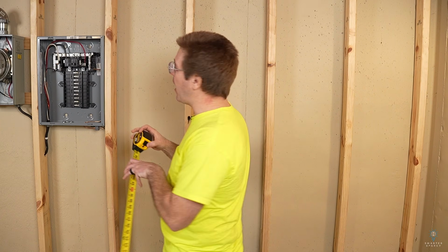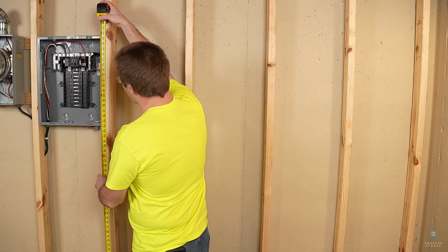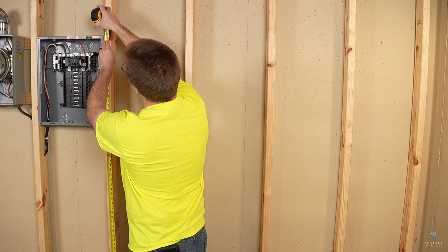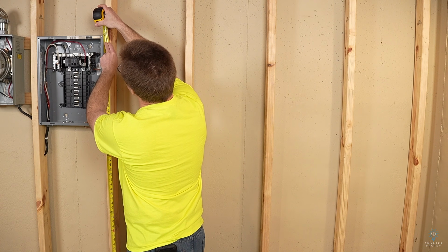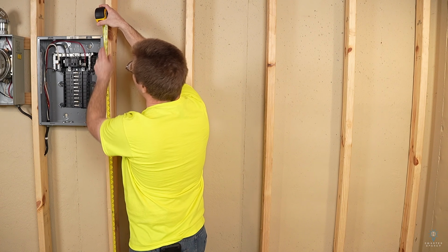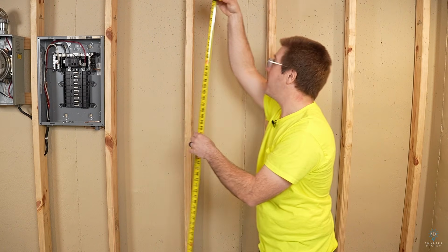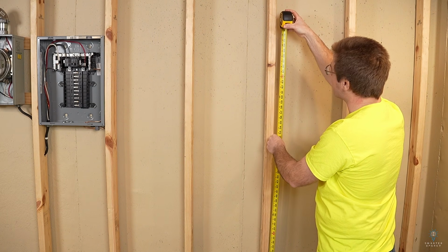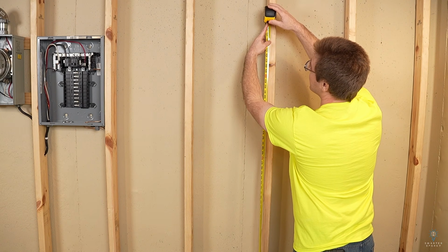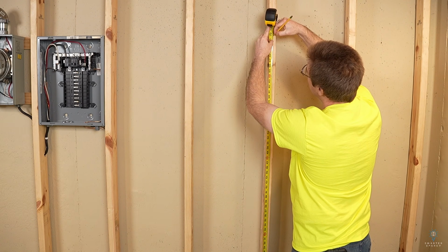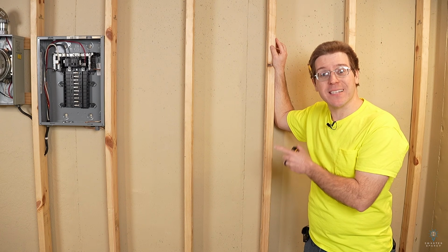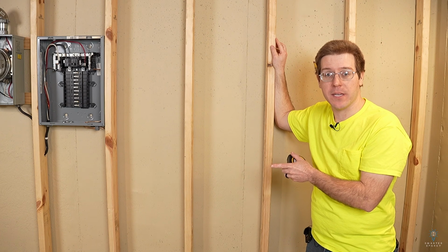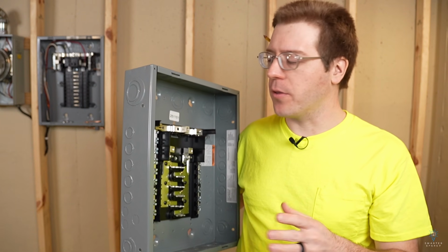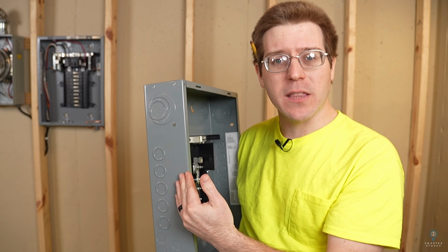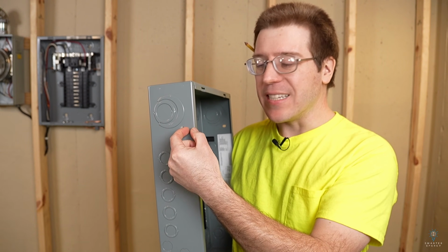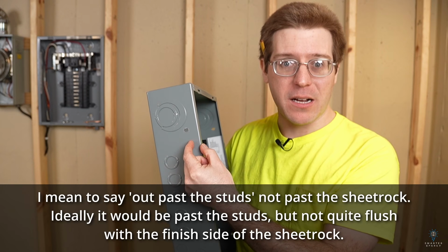So in order to figure out the height of this panel, I'm gonna go to the floor, and it looks like we are at 71¾ inches. So I am just gonna make a mark over here in my other stud pocket at the same 71¾. And now I've got a reference on how high the panel needs to be. There is another thing we need to consider though. Because this is going inside the wall, we're gonna actually need this sticking out past the studs a little bit.